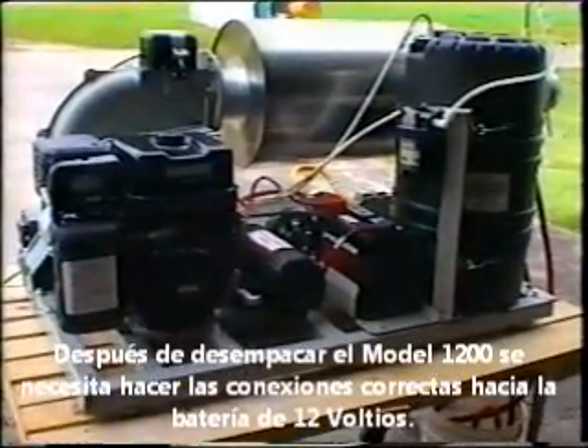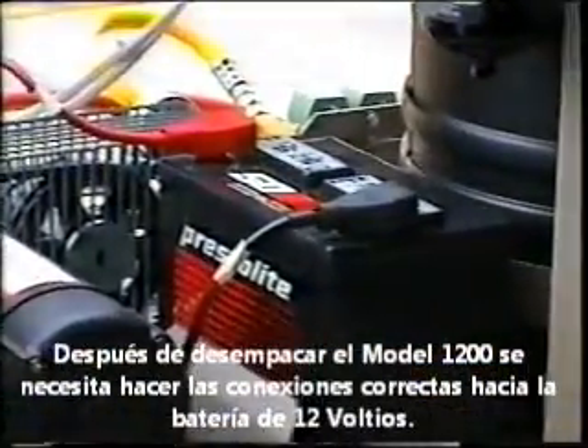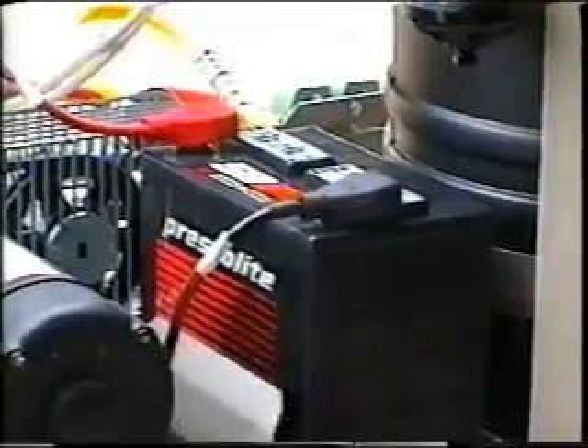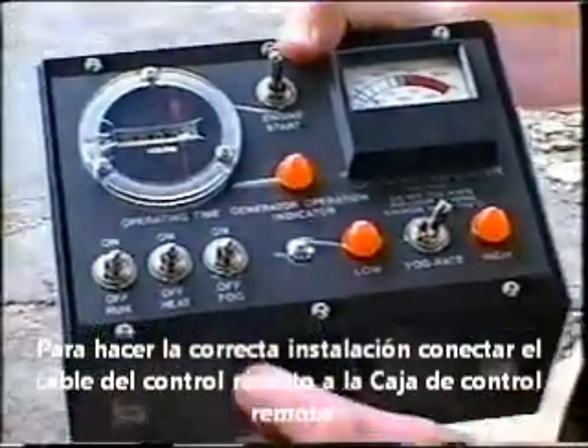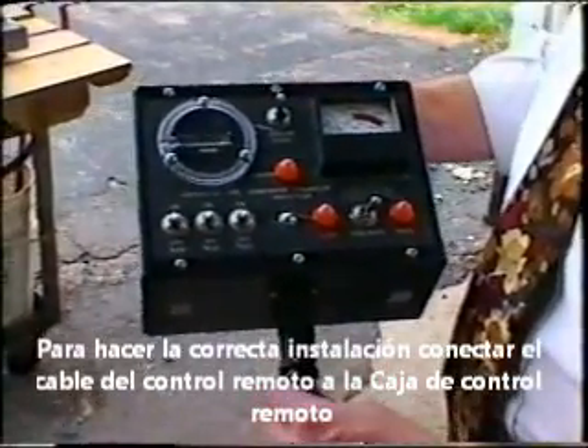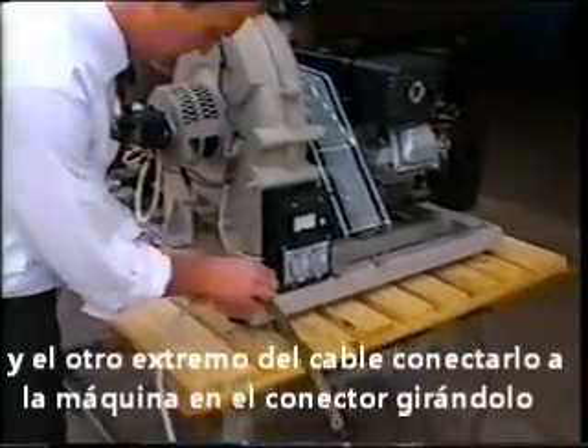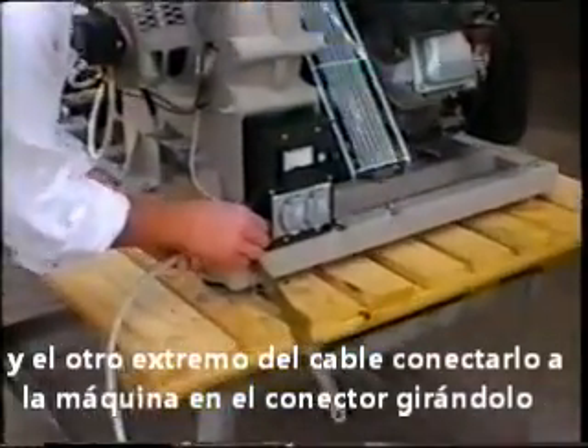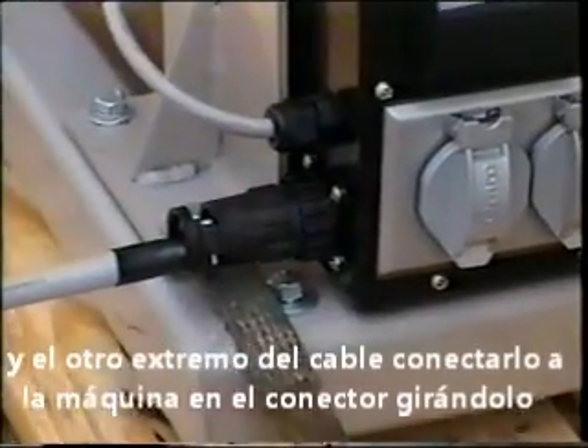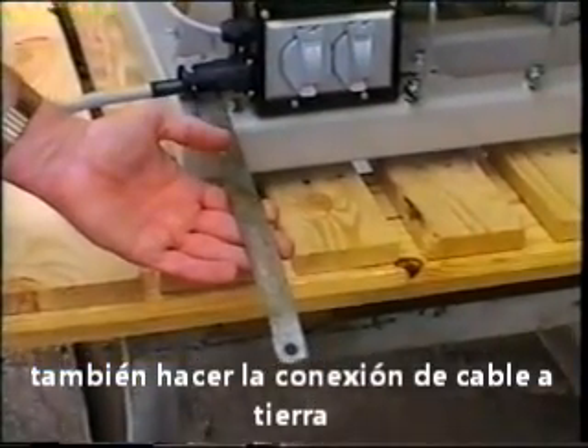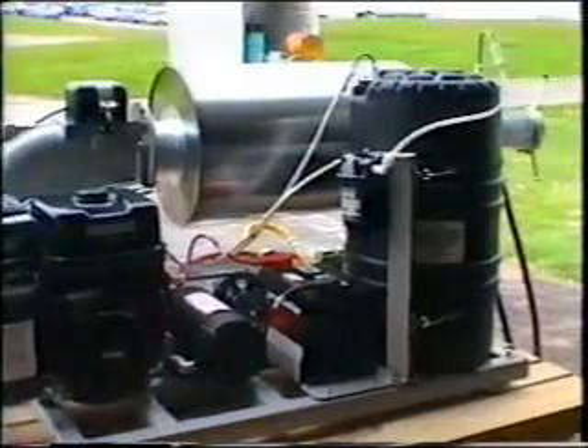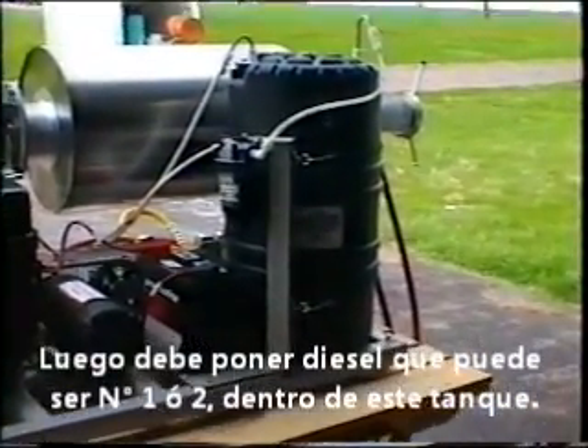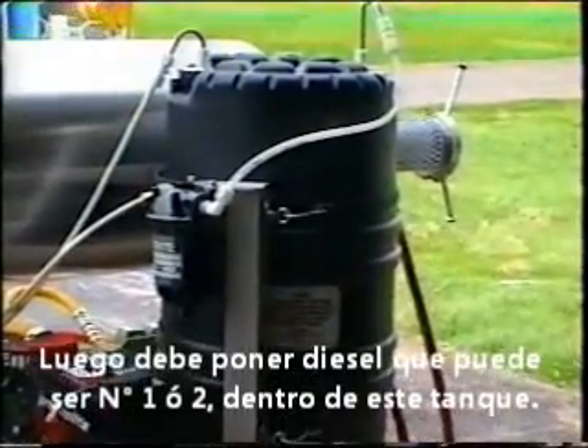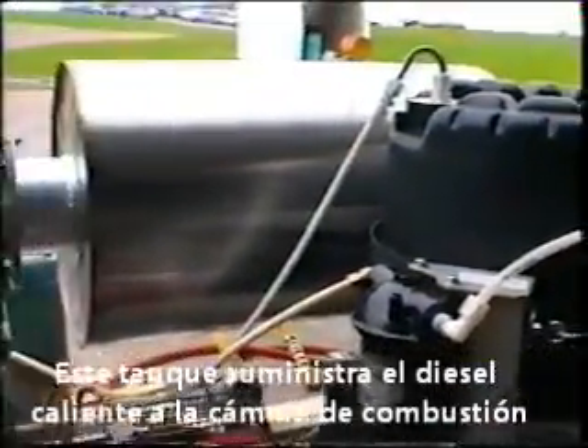After you have unpacked your Model 1200, you need to make the correct connections onto the 12-volt automobile battery. Make the correct connections from the remote control cable onto the remote control box, and the opposite end of the cable connects onto the machine with a twist lock type connector. Also make a ground connection onto the vehicle with this grounding strap. Next, you must put fuel oil, use number 1 or number 2 fuel oil, into this tank. This supplies the heating oil for the combustion chamber.